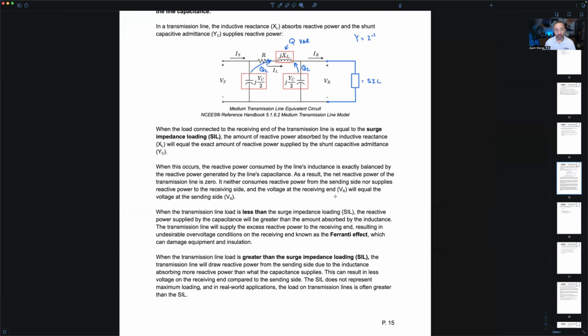What happens when the load is either less than or greater than our surge impedance loading? So when the load is less than the surge impedance loading value, then the reactive power supplied by our shunt admittance, which is the capacitors in our circuit model, is going to be greater than the amount absorbed by the inductance. What happens if this plus this is greater than this? Then what? We've got an excess amount of reactive power. Where does that excess reactive power go if our load is smaller than the surge impedance loading? It's got to go somewhere, right? Excess reactive power. In that case, the excess reactive power is going to go where? It's going to go to the receiving end.